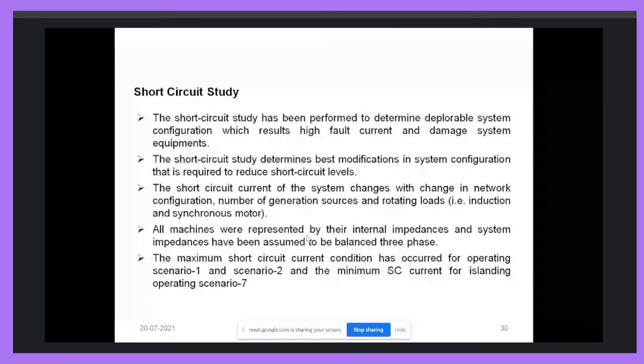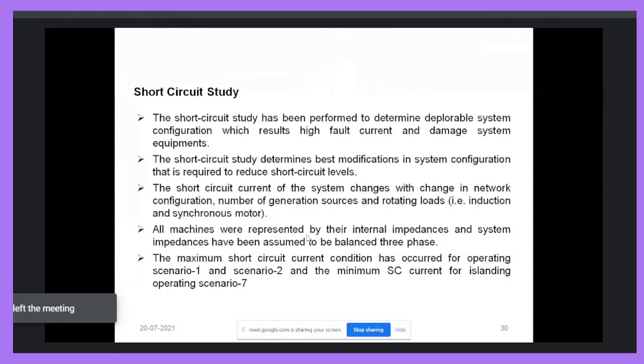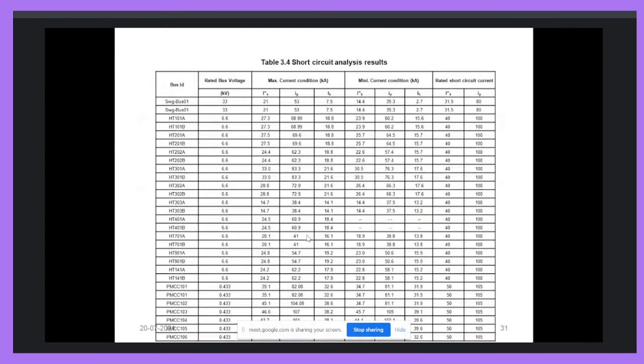We also performed short circuit analysis. The short circuit analysis is performed to determine the current of the system when the fault occurs, so we have the values of the system parameters under fault conditions. These are the results of a short circuit analysis. This is how we represent the results. Here you can see we have to represent the maximum current, the minimum current, and the rated short circuit current, because both minimum and maximum parameters are important. So what is the application of the maximum fault current? What is the application of the minimum fault current?